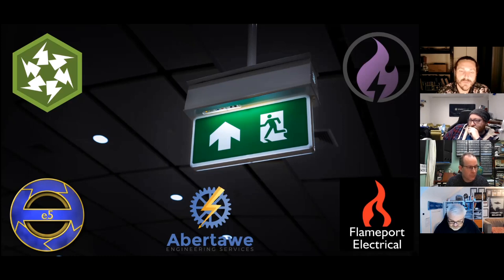And that's why it's important. When you're installing fire alarm systems, there's a process. You have a specification, as in, what do we need to install and why? That comes usually from fire risk assessment. It could be building regulations, it could be insurance. Then you design, you install, you commission, and then you maintain. So there might be a reason that that top floor was not required.